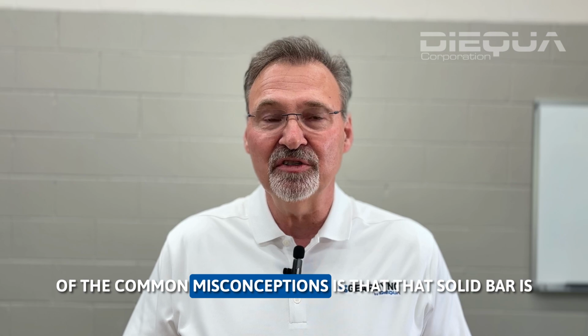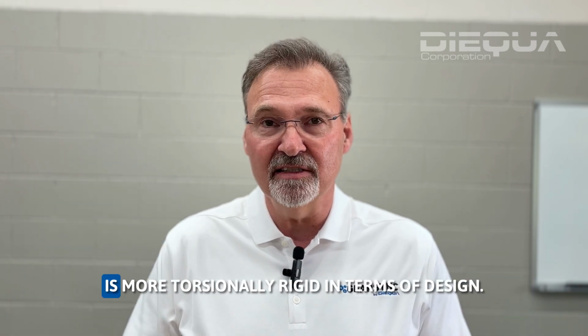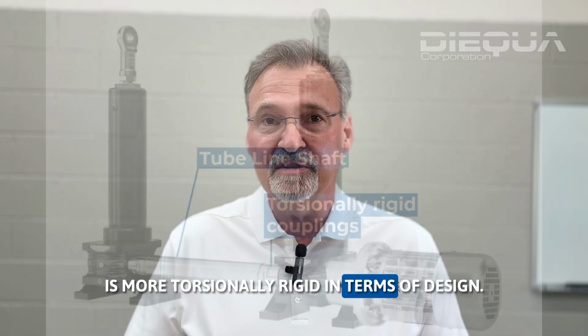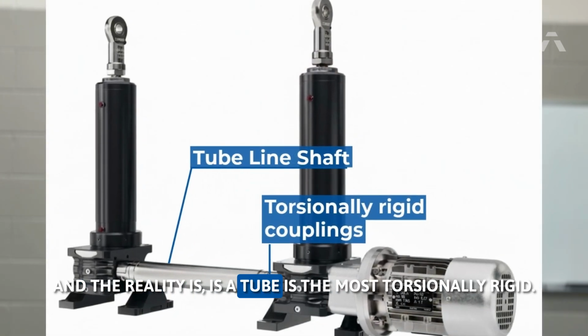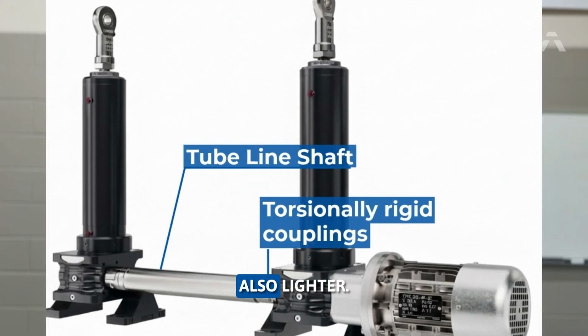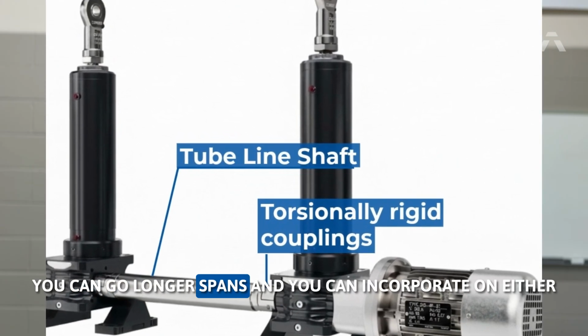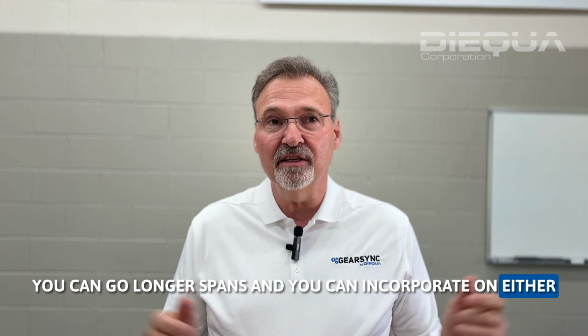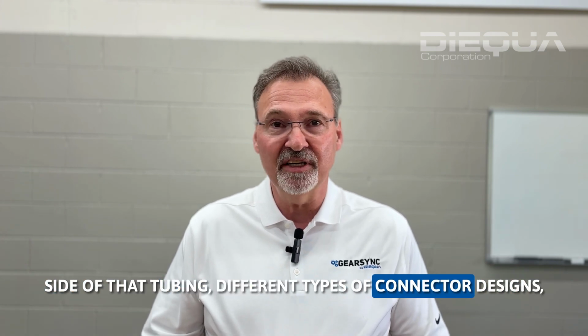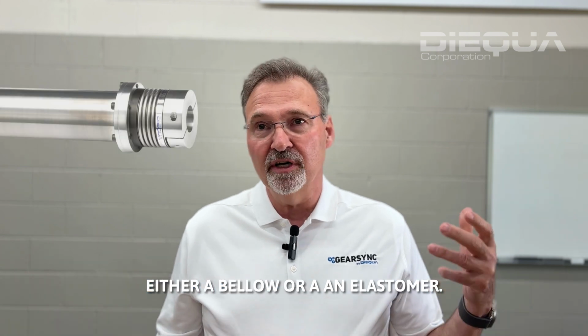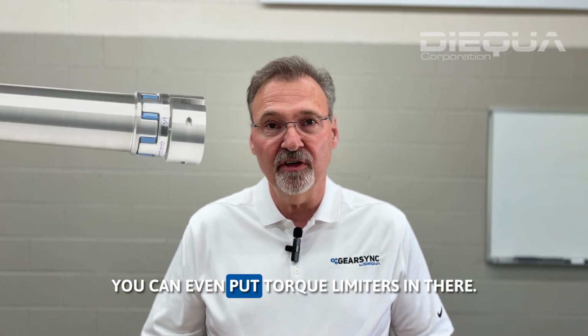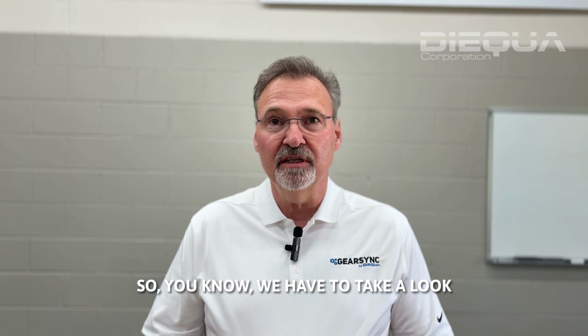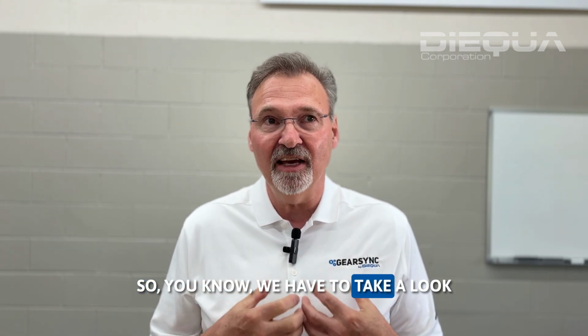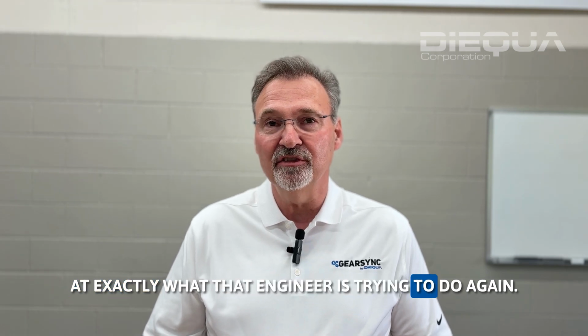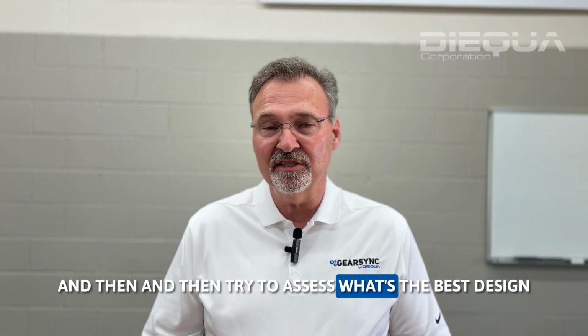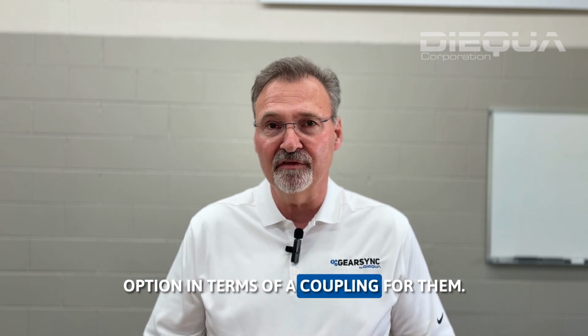One of the common misconceptions is that solid bar is more torsionally rigid in terms of design. The reality is a tube is the most torsionally rigid. It's also lighter, you can go longer spans, and you can incorporate on either side of that tubing different types of connector designs, either a bellow or an elastomer. You can even put torque limiters in there. So we have to look at exactly what that engineer is trying to do again, and then assess what's the best design option in terms of a coupling for them.